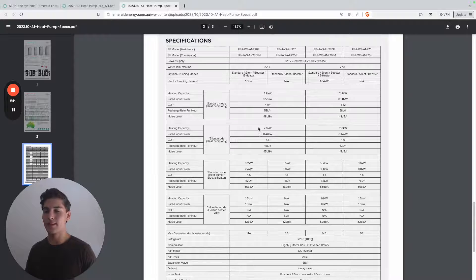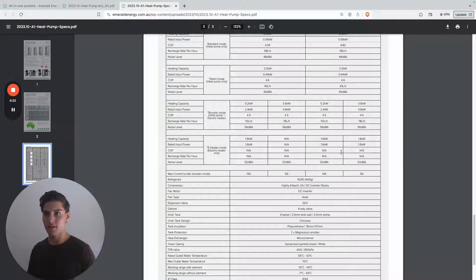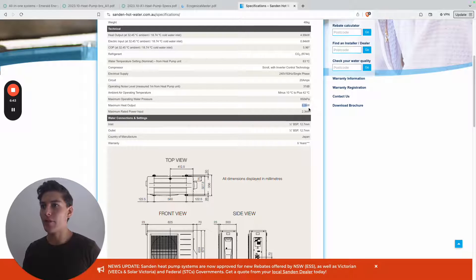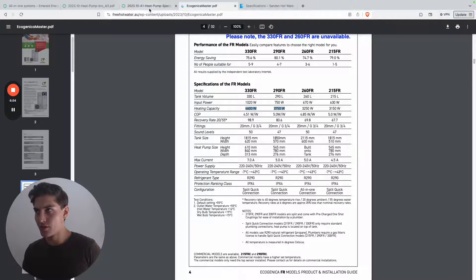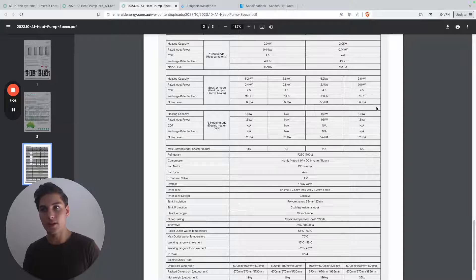It looks like the compressor used for both the 220 and 270 litre units is the same, based on their input power and heating capacity. The recharge rate is very efficient but quite slow. Comparing to split unit systems: Sanden has a 2.3 kW input but 6 kW output; Ecogenica tends to operate upward of 3 kilowatts output. So this system is a little slower at heating hot water, but it's very efficient and it doesn't need to be extremely quick.